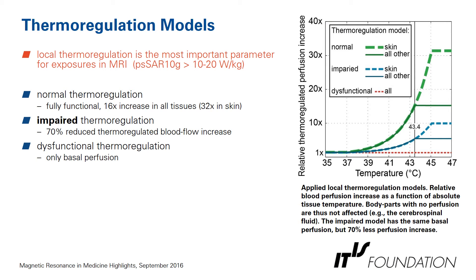Moving to temperature results, we need to include a thermoregulation model, as local thermoregulation is the most important parameter for exposures in MRI where local SAR values exceed 20 W/kg. We included a normal thermoregulation model — a fully functional model with a 16-fold increase in all tissues and up to 32-fold increase in skin. We also included an impaired thermoregulation model with 70% reduced blood flow increase, and a dysfunctional thermoregulation using only basal perfusion without any perfusion increase with temperature.